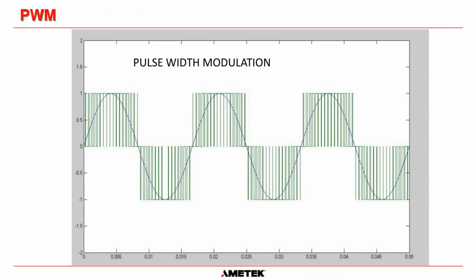Okay, now look, this is the important thing to remember for pulse width modulation. The amplitude is not changing. So this is 135 volts DC for a normal 60 cell system. Okay, that does not change ever. That's what we're switching if the charger is on and the battery is good. And also, if you measure the frequency of each of these pulses, the frequency, although my drawing is absolutely terrible, the frequency is not changing. Okay, that's still remaining the same, and the frequency used is about 8.5 kilohertz. We are switching at 8,500 times a second. It's crazy, the speed that we switch our IGBTs on in our pulse width modulated system.